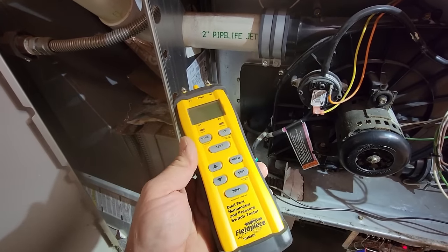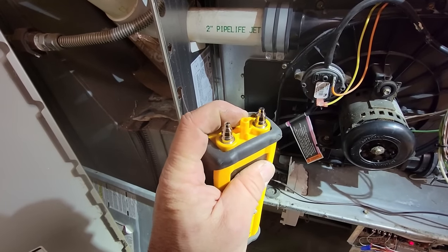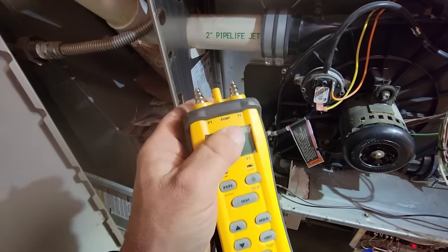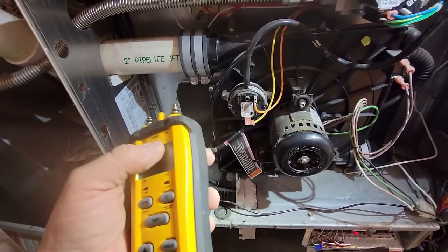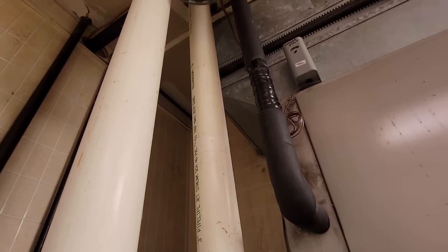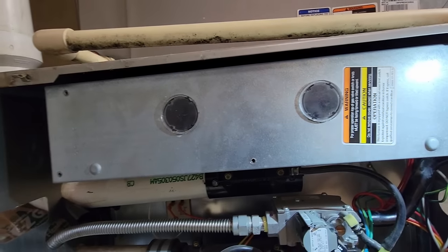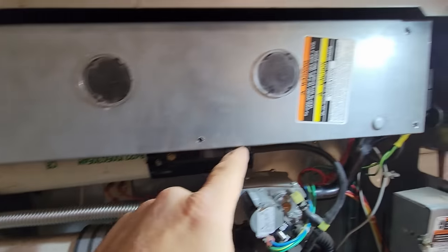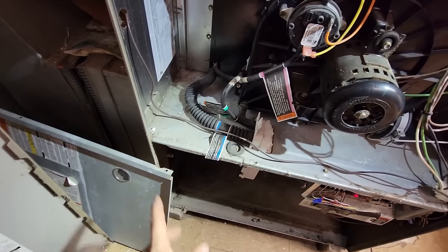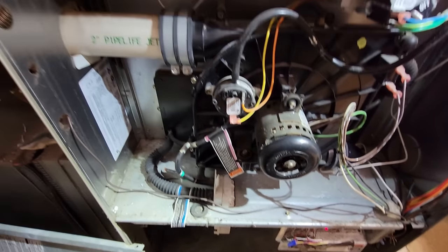Fieldpiece doesn't sponsor me or anything as of yet. This has been a really good tool. It has a vacuum pump in it so you can test the pressure switch, and it has a continuity checker across here - so if you wanted to know if that switch is opening and closing, or if you have an adjustable one, you can actually set it up with this thing. I went ahead and cleaned that up, just put some white tape over that. There ain't nothing coming through it. We're going to go ahead and clean up the flame sensor, check the igniter's resistance, clean the condensate trap, change filters, check fan blades, motor amp draws, and electrical connections.